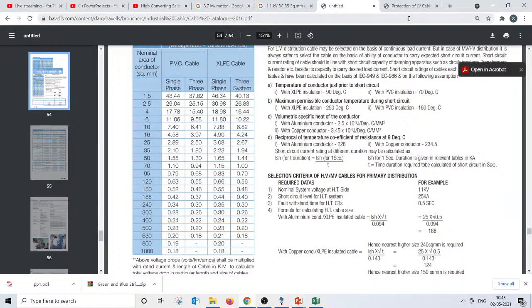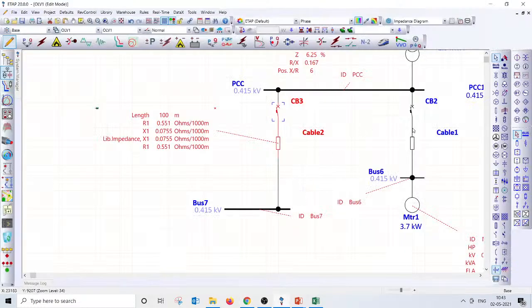But in LV, the short circuit current is too low, and the full load current is more. In order to carry this full load current, you will go with a higher size, and hence that will easily take care of the short circuit also. That's the logic. That may not really work when you have a very small size cable, a very small load, and a huge fault current.